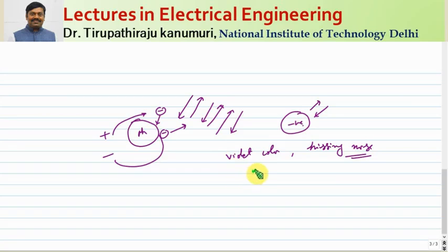And the second effect of this corona is because we know that the conduction will start only if the voltage at the surface of the conductor is greater than 30 kV per centimeter. This is 30 kV per centimeter. So if you take your AC supply voltage, because it is continuously varying like this, the electric field also goes on varying because it depends on the potential. So the electric field will be greater than this 30 kV per centimeter only for some time, again it will decrease, again for some time and decrease.